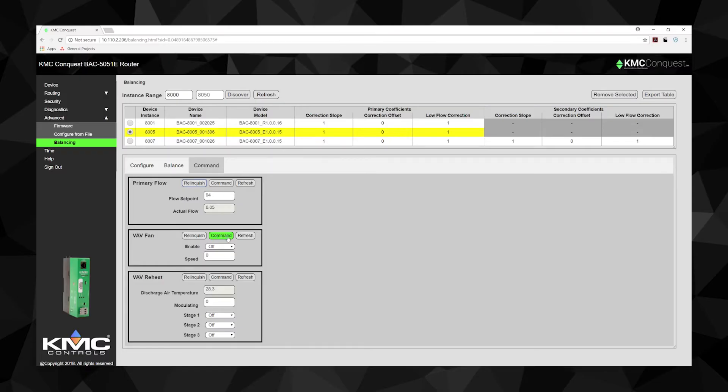One thing to note, if you are balancing a fan-powered VAV box, we suggest you click the Command tab found on the balancing page before you begin the VAV balancing process. Here, select the Command VAV Fan option. This will allow you to command the VAV box fan for balancing.